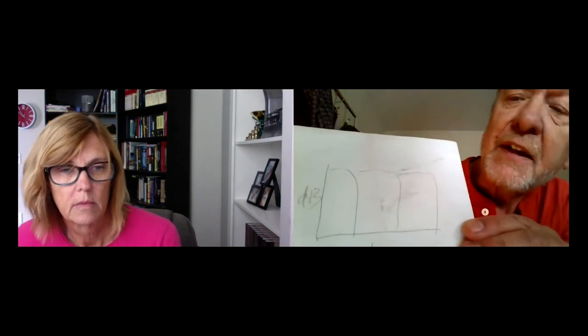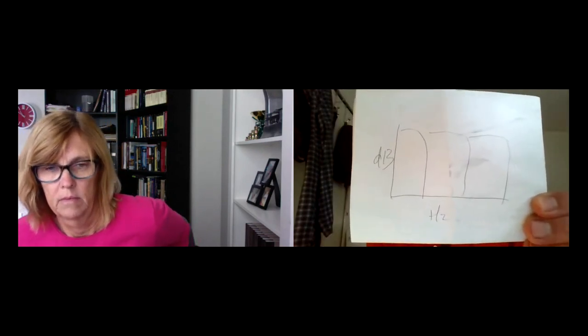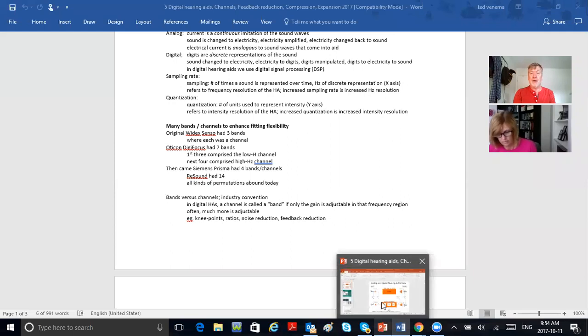The original Widex, the first digital hearing aid in 1997, had three channels — each channel fairly wide. If you think of a frequency response from 125 Hz to 8,000 Hz, you've got pretty wide channels — three big regions, like lows, mediums, and highs — and you could raise or adjust those to accommodate the client's hearing loss.